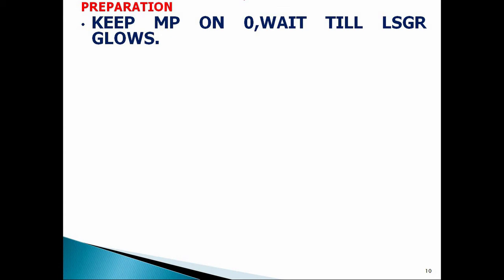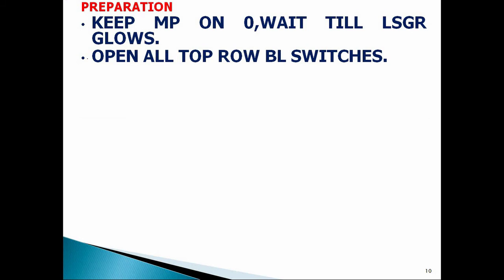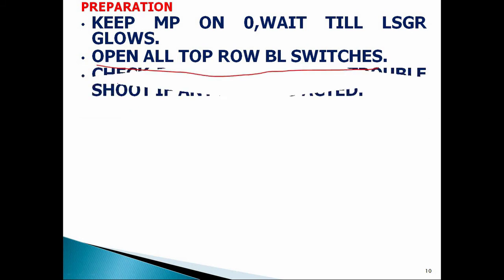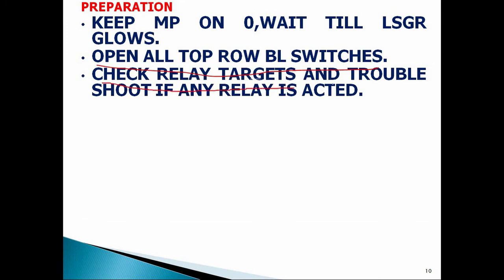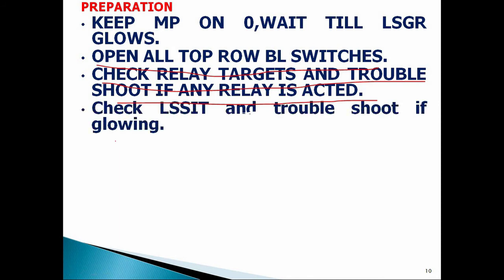And on run only, he shall keep MP on 0, wait till LSGR glows. Wait till LSGR close. Then open all top row BL switches and then check relay targets and troubleshoot accordingly if any relay is acted. Here, LSSIT also is supposed to check.